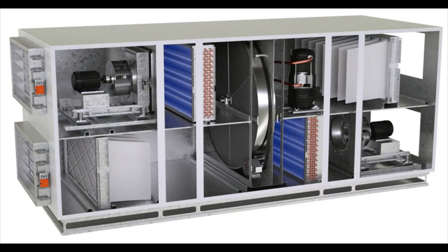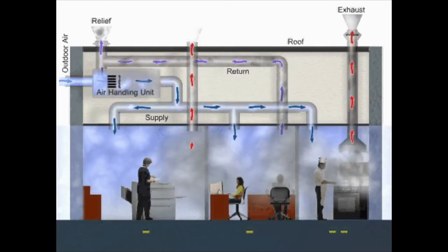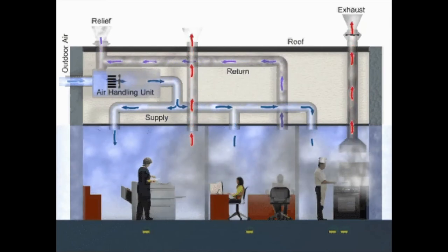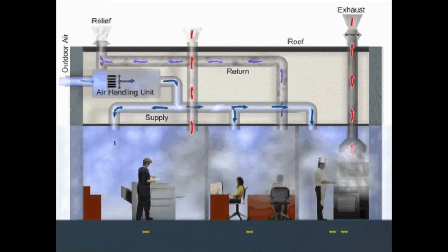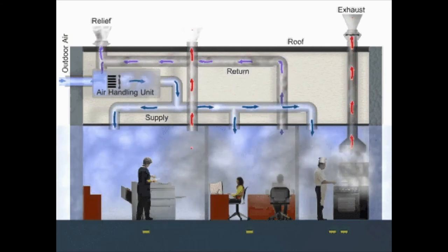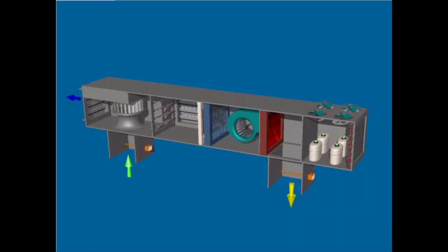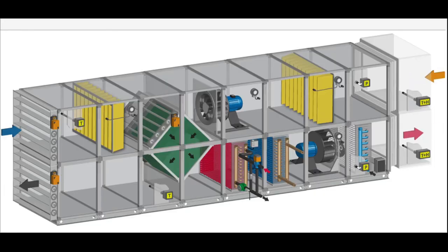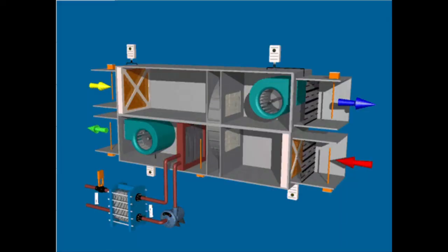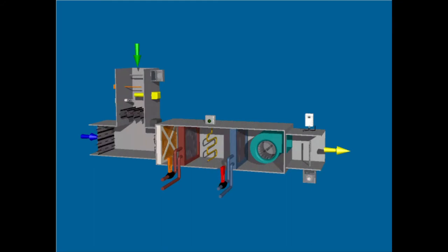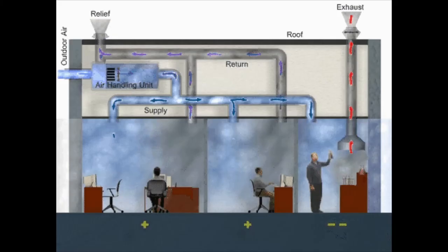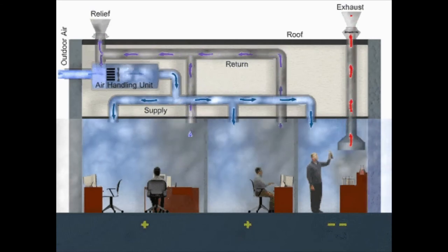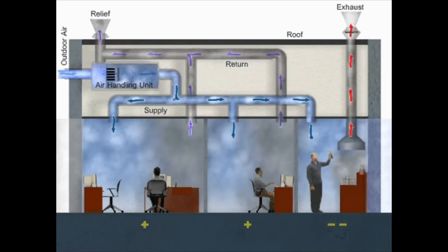For your pandemics, you want to have this in your sequences. Sequence of operation is something that is automated throughout modern buildings today. You have pre-programmed sequences programmed into a circuit board and then inside a computer, or linked to a computer, that allows your building to automatically operate its air handling systems and all the other building systems, hospital systems, whatever it is out there, lighting systems. So they turn on automatically, they turn off automatically, they ramp up automatically, they ramp down automatically.